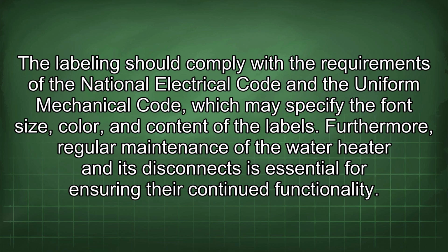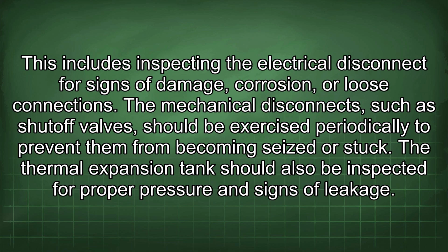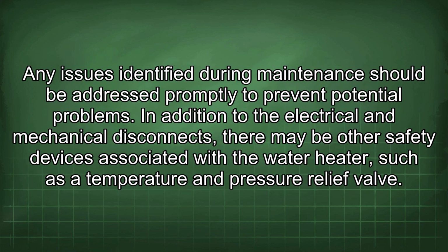Furthermore, regular maintenance of the water heater and its disconnects is essential for ensuring their continued functionality. This includes inspecting the electrical disconnect for signs of damage, corrosion, or loose connections. The mechanical disconnects, such as shut-off valves, should be exercised periodically to prevent them from becoming seized or stuck. Thermal expansion tank should also be inspected for proper pressure and signs of leakage. Any issues identified during maintenance should be addressed promptly to prevent potential problems.